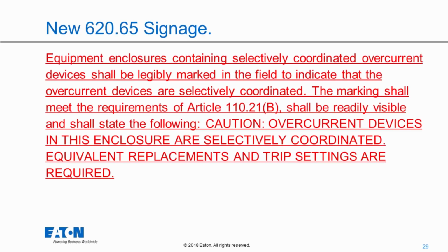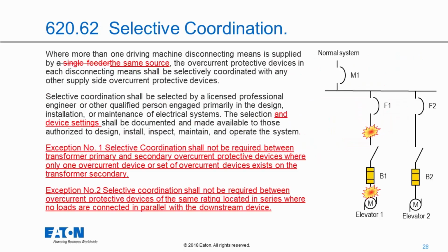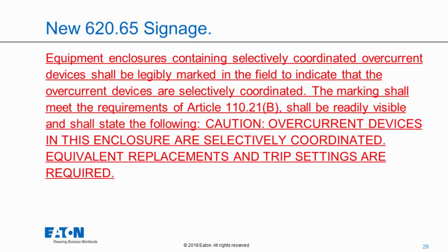So let's say that we have, obviously, the enclosure where the elevator disconnect is located. So if we go back to that one-line, elevator B1, that enclosure would need to have that field marking on it. But I would also consider that M1 and F1 also would need that marked as well because they are part of that system. Okay.